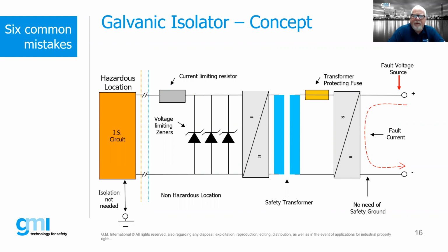So what happens under a fault condition with intrinsic safety in a galvanic isolator situation? A potential fault current hits the transformer and stays within the safe area—it's not transmitted into the hazardous area. The whole concept of intrinsic safety is to limit the amount of energy that could be released into the hazardous area under normal or fault conditions. That's the idea of having an intrinsically safe barrier or associated apparatus in the first place: to limit energy transmitted from the safe area into the hazardous area. That's how a galvanic isolator works.